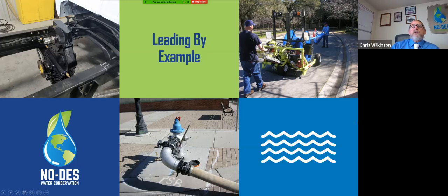The reason why we do this is because this is a dry barrel hydrant, and that's mostly throughout the United States. When you open that up, you have a drain or weep hole at the bottom of the barrel, and that allows water to come out here and flood the area. So what we do is we close this valve, open the hydrant full open to where that bleed hole shuts, and then we use this valve to open and slowly fill the machine. That's all it's for. You can see the 90 degree elbows here.